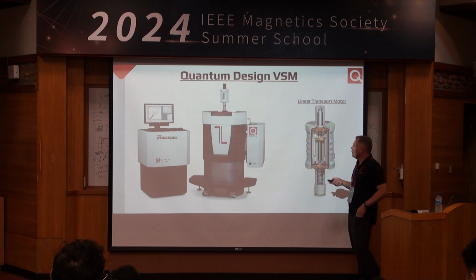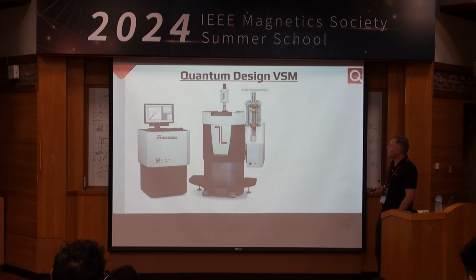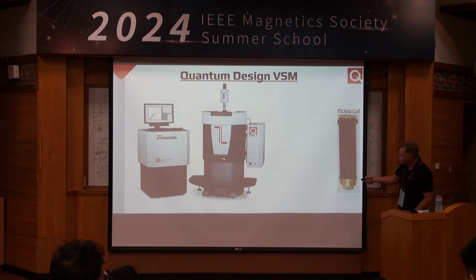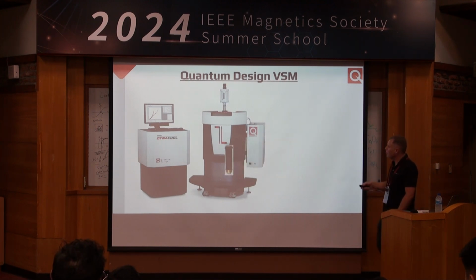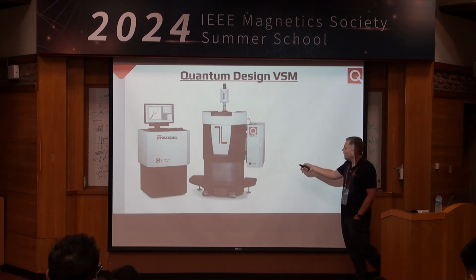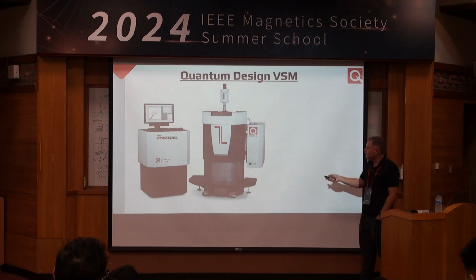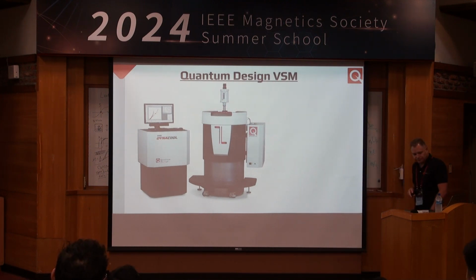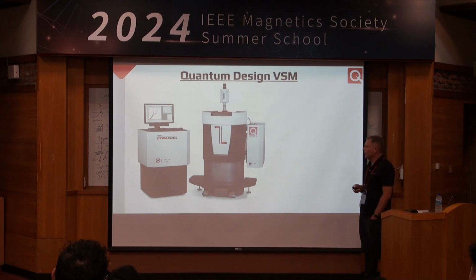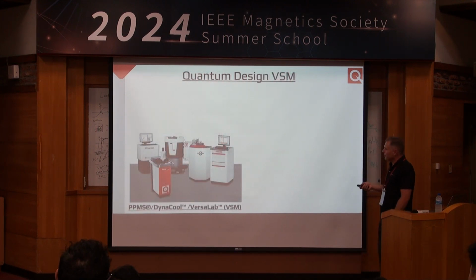So we have a motor that we can put on top of here to vibrate the sample. That goes up there. And then we have a specialized puck that goes inside the system. This is our pickup coil. And then the electronics, basically the lock-in and the thing that drives the motor, exist here in this electronic rack. So this is our take on the VSM. Let's go into a little bit more detail, and it works in our entire family of PPMS product lines here.